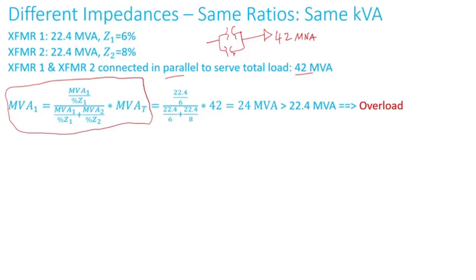Plugging in the numbers, transformer one will carry 24 MVA out of the 42 MVA load. Notice that transformer one is only rated 22.4 MVA, so transformer one in this case will be overloaded.